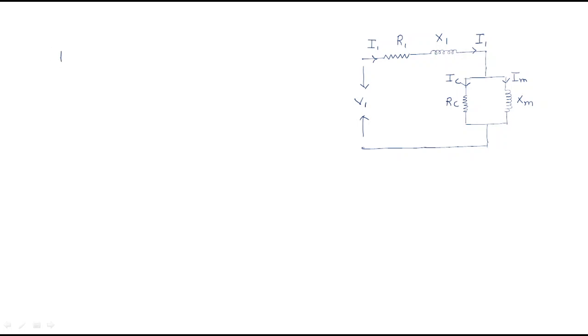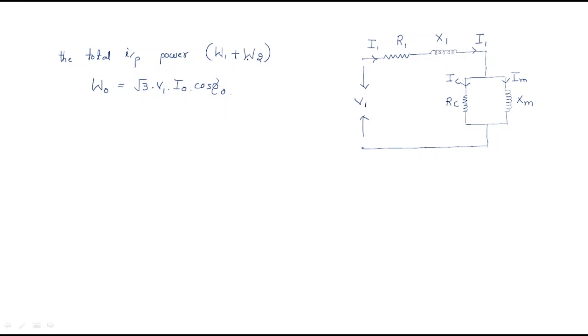For the calculations: the total input power applied to the induction motor under no-load is denoted as W0. W0 equals root-3 times V1 times I-naught times cos-phi-naught. This is also equal to W1 plus W2, the sum of the two wattmeter readings. V1 is the applied voltage and I-naught is the no-load input current — I1 and I-naught are the same here.